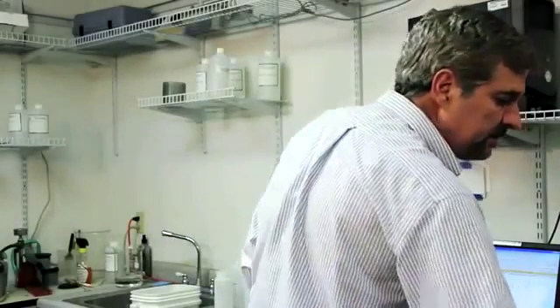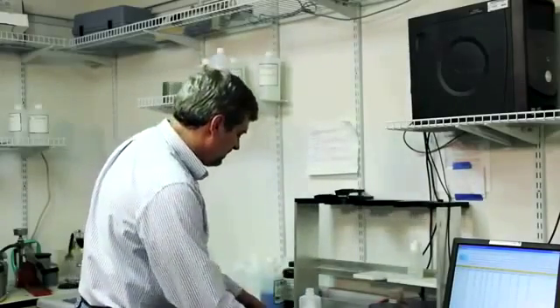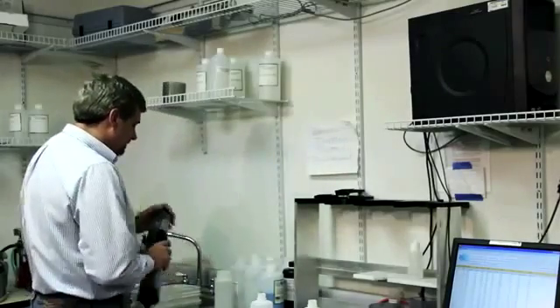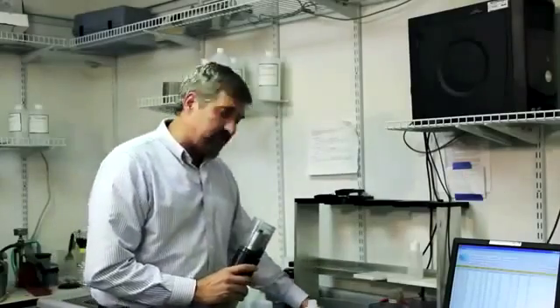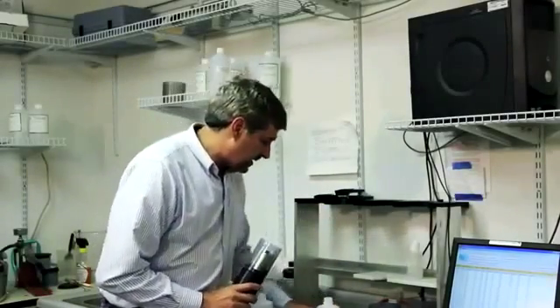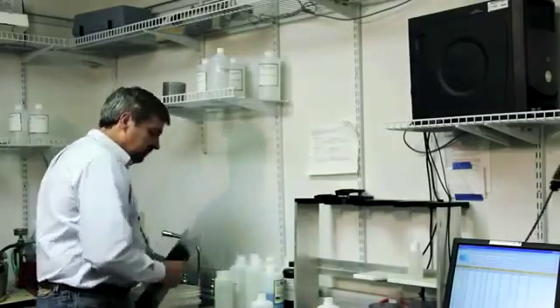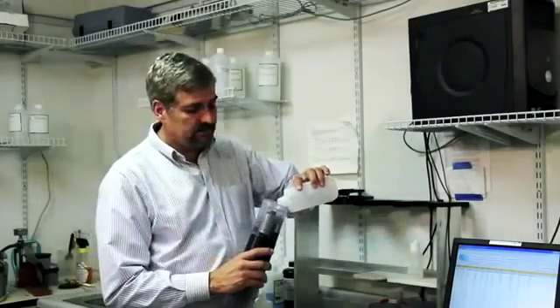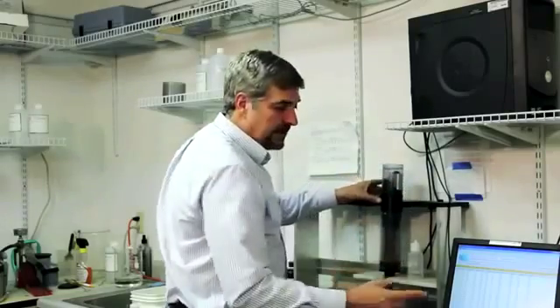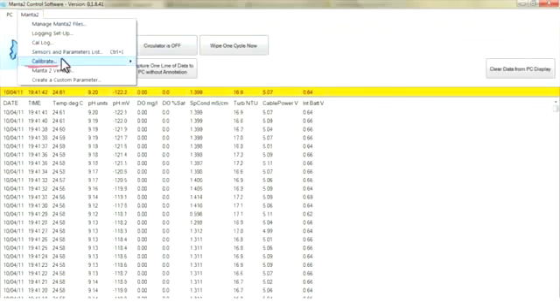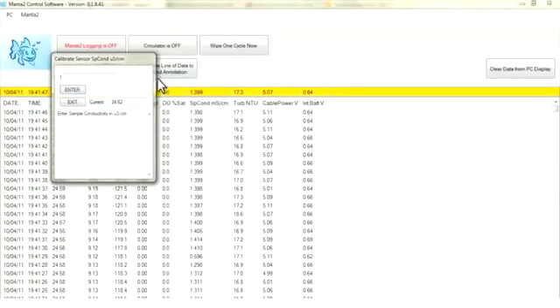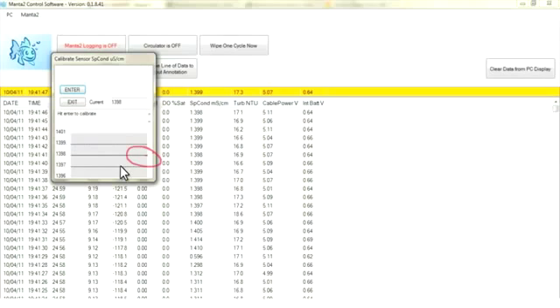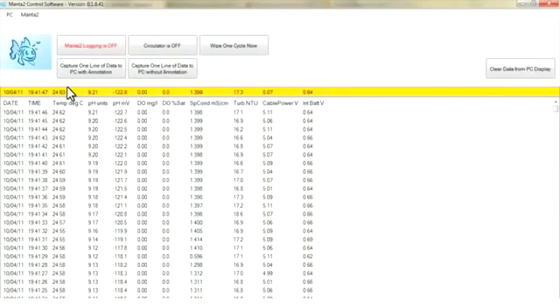And I'm going to calibrate conductivity. Rinse with my DI water. And remember I'm eliminating the rinse. Rinse with my conductivity. Cover up my sensors. Back to the screen. Manta 2. Calibrate. Specific conductance in microsiemens per centimeter. I'm doing fresh water calibration. I'm using 1412 microsiemens. Enter. Wait till stable. It's stable. Hit enter. Yes to accept. And we're done with that.